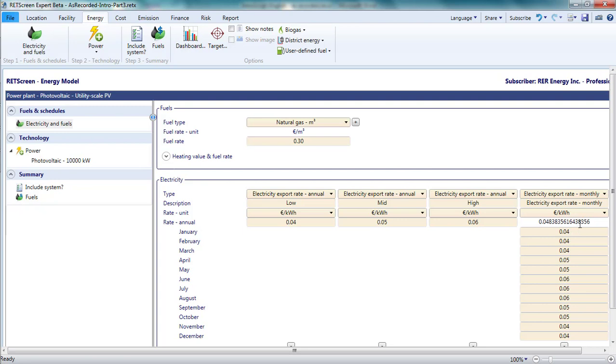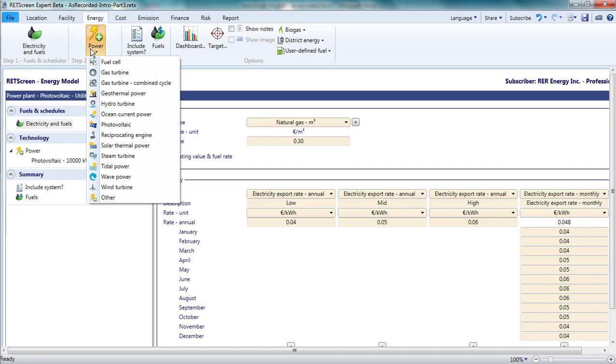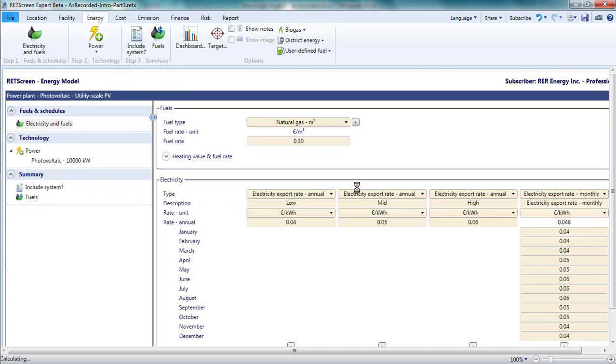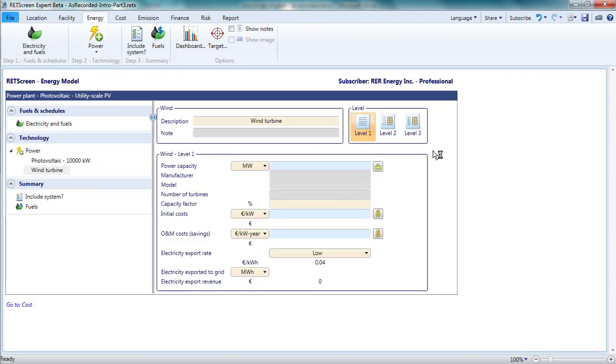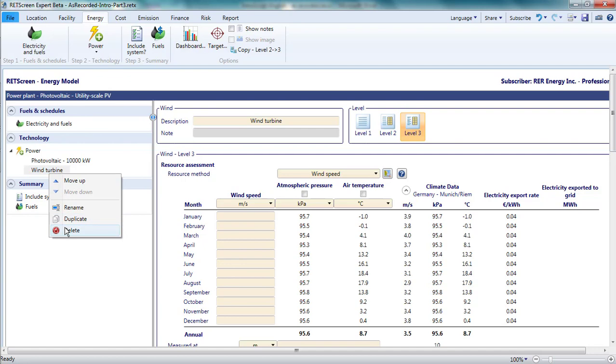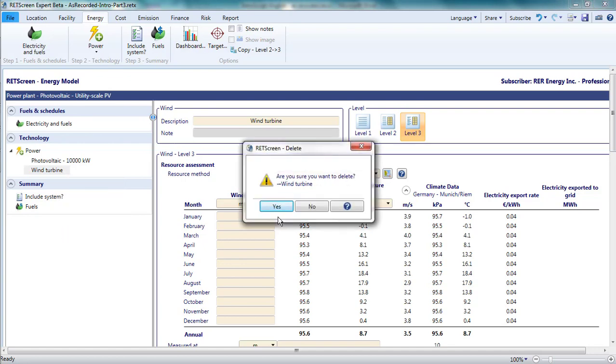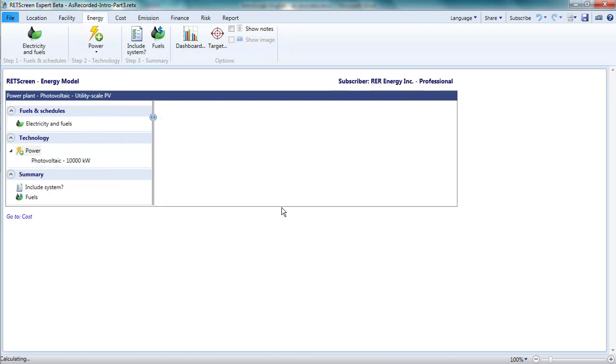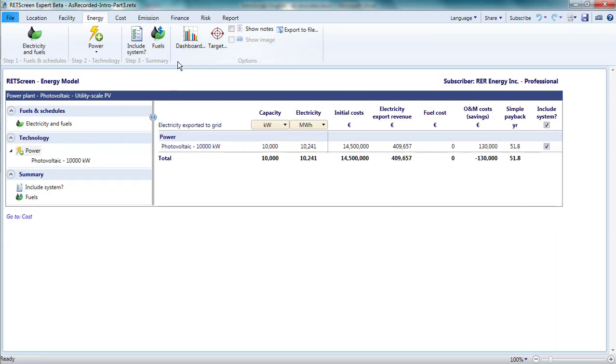For most technologies, RETScreen will multiply the annual average calculated from the monthly data by the annual electricity exported to determine the annual revenues for electricity sales. But for wind and photovoltaics, it can also do a monthly analysis, in which the monthly electricity exports will be calculated individually and multiplied by the tariff for that month. In this way, the analysis reflects any seasonal correlation between electricity tariffs and the wind or solar resource.